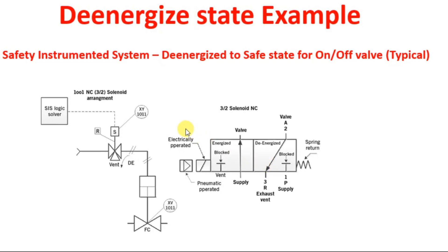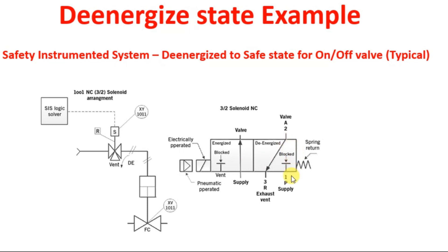The main valve part is known as an actuator, and this actuator is being driven using instrument air. The instrument air line shows air being sent into the actuator through the solenoid valve. Under normal operating conditions, when the solenoid power is energized during normal plant operation, the instrument air goes into the valve actuator body to keep it in the open position.